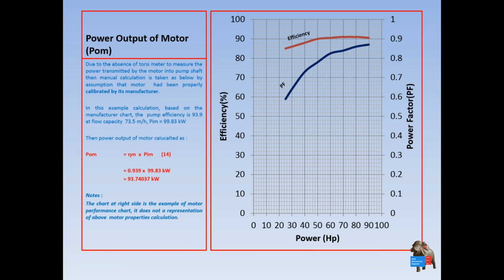Okay, and then we want to know the power output of the motors. This is quite tricky. The power output of the motor is usually called the shaft power of the motor. Then you need the motor performance data sheet. So let's say you are running the motor at this power. You have a power factor, and then you have efficiency here.